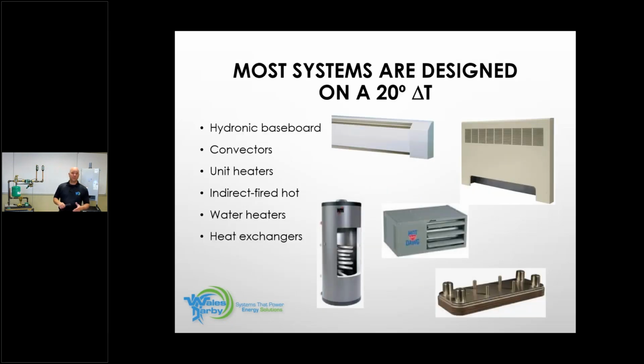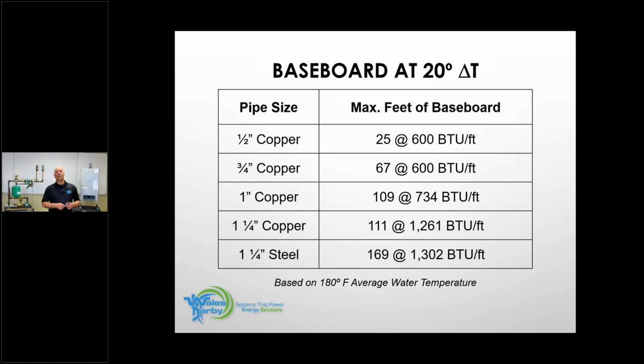Additional items here calculated most of the time for 20-degree delta T's: baseboard, convectors, Modine hot dog, NTI indirects. You could see up to a 30-degree delta on the indirects. Plate exchangers, we start out normally designing them with a 20-degree delta. Most of the time, you could see those vary, but that's about where we live, for out of the box. That's where we start. So almost everything we work with, again, is designed around that 20-degree delta. So this right here, this is just going through and letting us understand the ability of a pipe to carry BTU.